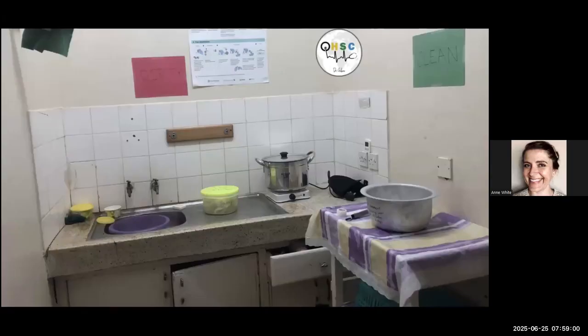And so this is just one image of a disinfection reprocessing room I helped to set up in Kenya. Straight ahead, you can see a red sign on the wall that says dirty. In the sink, that is where the used equipment would come from the unit that needed to be disinfected. The equipment then would move from left to right around the counter. On the right-hand side of the image, up on the wall, you can see a green sign that says clean. So the equipment always needs to move from the dirty area to the clean area, not mixing up equipment back and forth and contaminating it between the two.